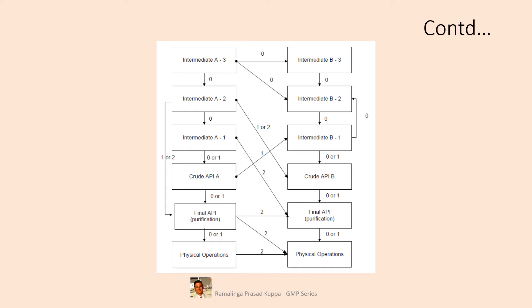Any variations to these recommendations must be scientifically justified and fully documented. Scientific justification can be done only by statistical risk assessment, focusing on ease of cleaning, toxicological characteristics of the intermediates and their impurities, maximum daily dosage and batch size of the next product, solubility, and experience in cleaning the residues.